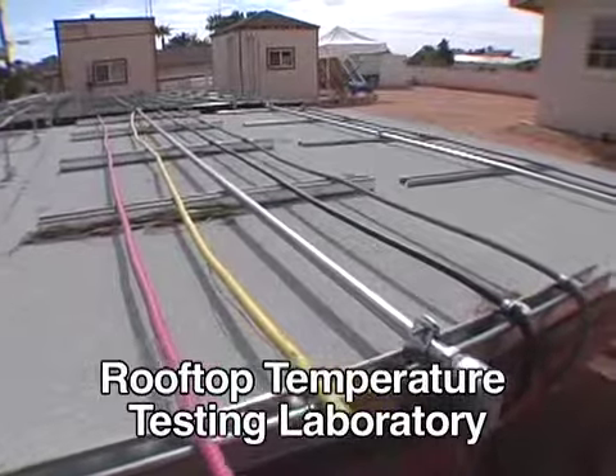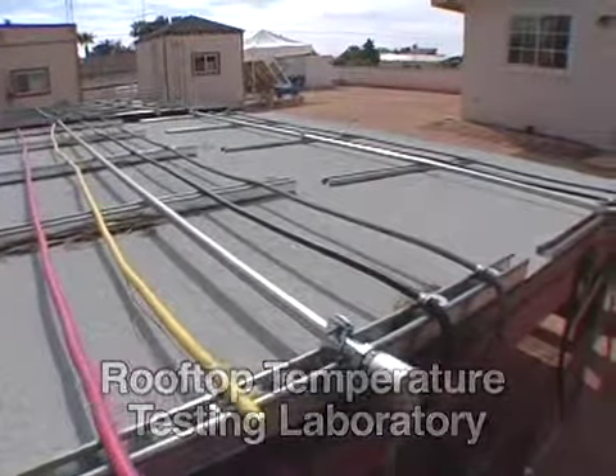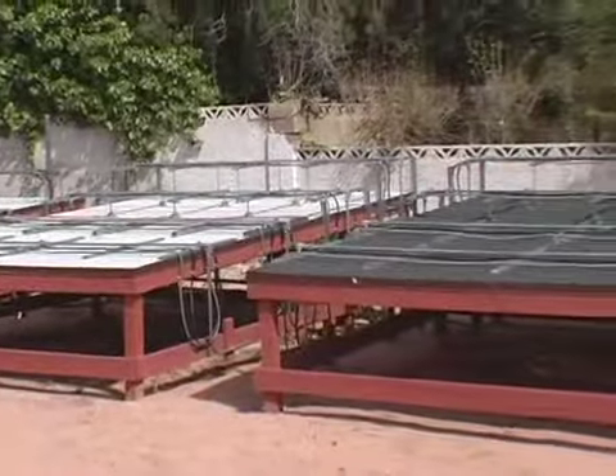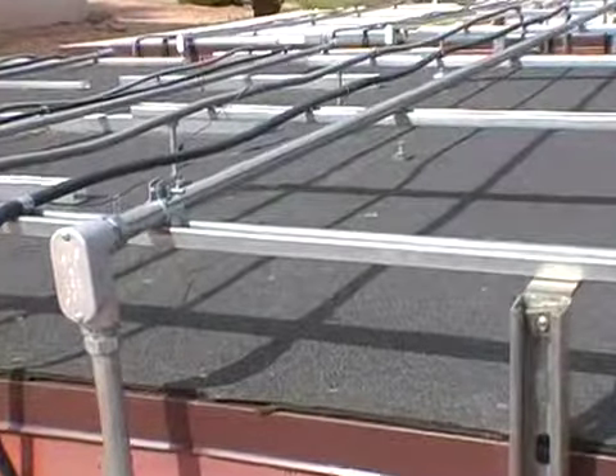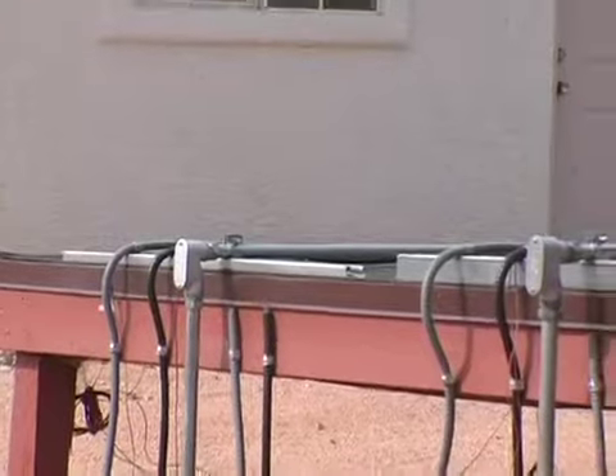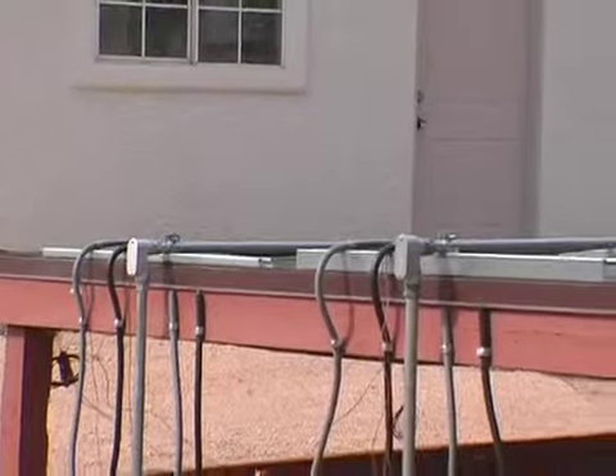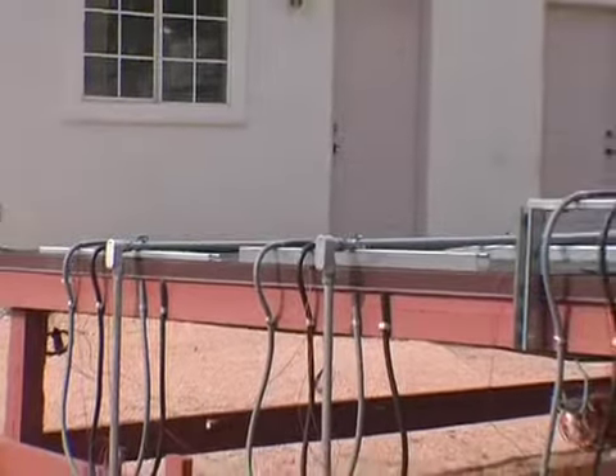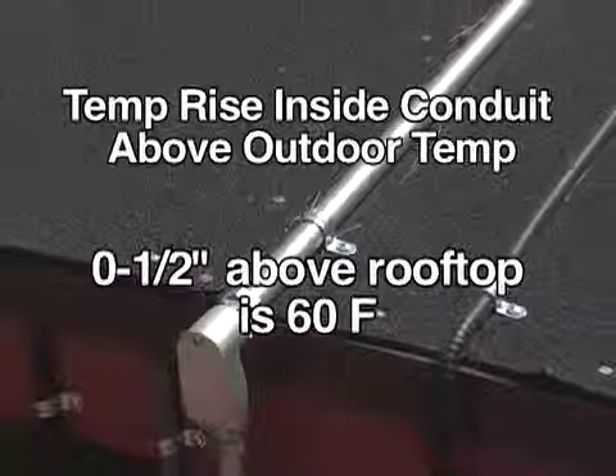The Rooftop Temperature Testing Laboratory performed research to determine the temperatures inside conduits which are located on rooftops in sunlight. This research was then published in a peer-reviewed IEEE Transactions paper and also certified by an independent, nationally recognized testing laboratory. The research discovered the following. If you know the outdoor temperature and you know the height of the conduit above the roof, you can determine the interior conduit temperature, which is the ambient temperature to which the insulation is subjected.